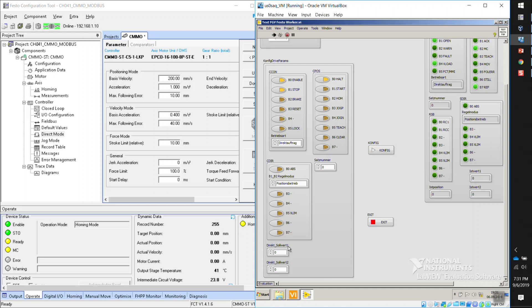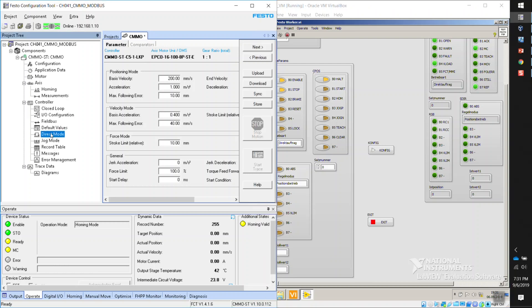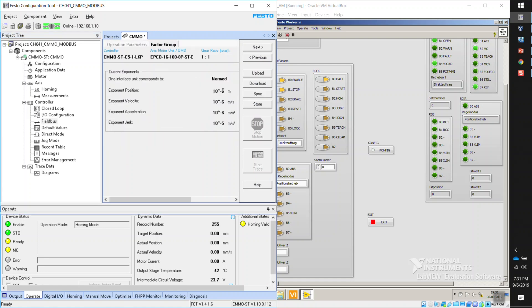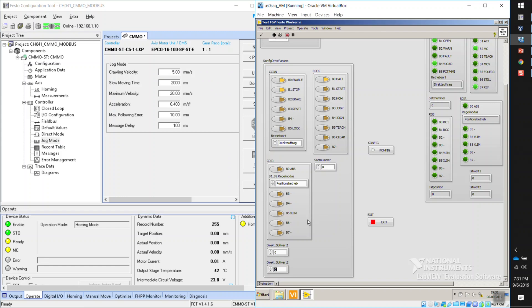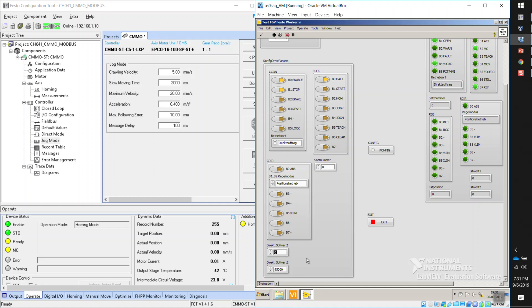So what next? Let's execute a move. So here, this is going to be the position. And in this case, since I'm using a factor group of minus six, I'm using an actuator of 100 millimeter stroke. So let's write 95,000, which is going to be 95 millimeters. And I'm going to write a speed here. Remember that in direct mode, the speed is specified in percentage. So I'm going to specify a five percent in the speed. So I'm going to write this. So that is written. And now I'm going to toggle this bit start and then execute a write, I guess, or config.